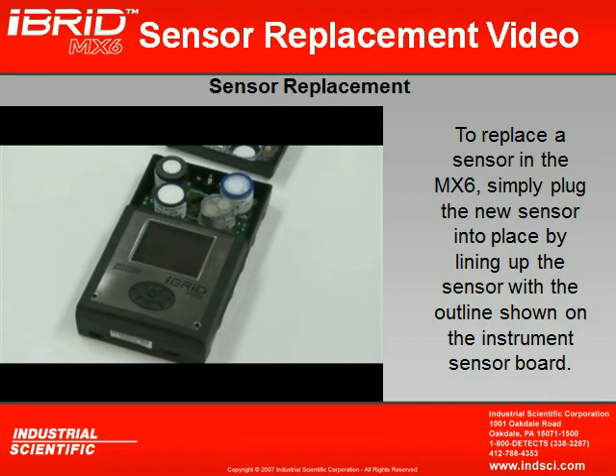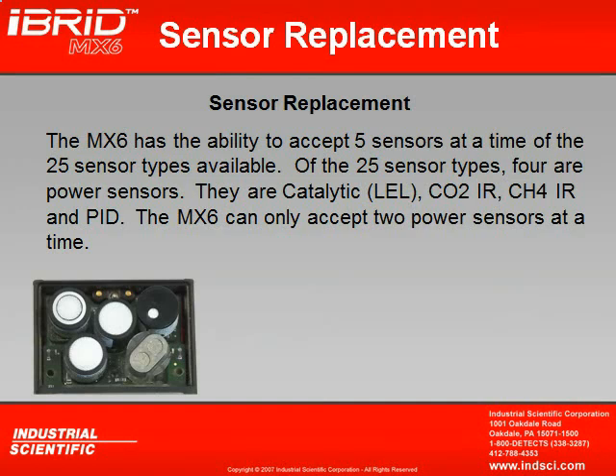Now the MX6 has the ability to accept up to 5 sensors at a time, of the 25 different sensor types available. But of these 25 sensor types, there are 4 that we call power sensors. The 4 power sensors are the catalytic sensor, CO2 IR, methane IR, and the PID. Now the MX6 can only accept 2 power sensors at a time. In other words, I cannot configure my MX6 for LEL, CO2, and PID. Only 2 power sensors can be placed inside the instrument.